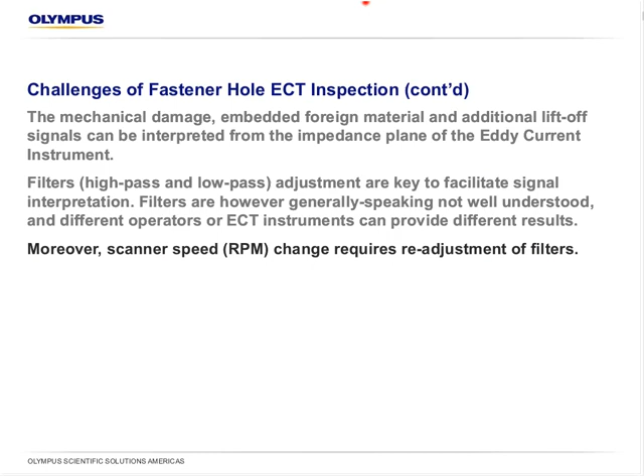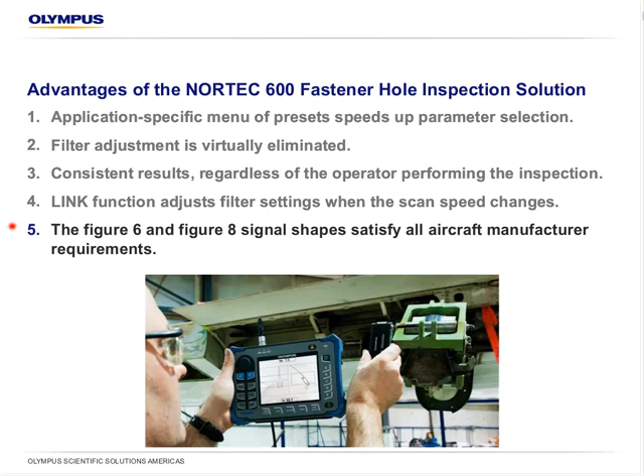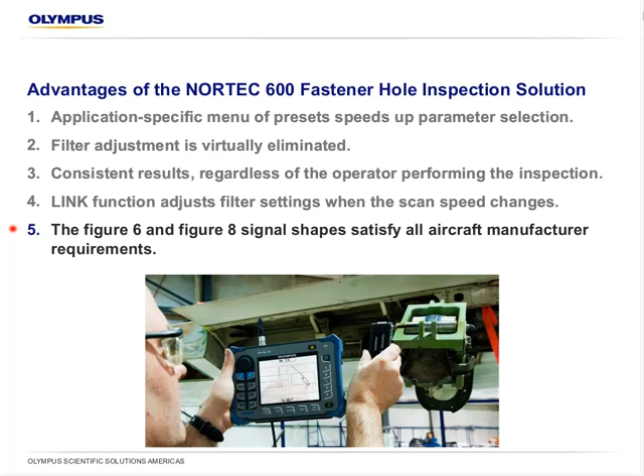So, the advantages of the NORTEC 600 fastener hole inspection solution. First of all, and I will talk quite a bit about it, it has an application-specific menu. Basically, it's presets that speed up the parameter selection. There is some filter adjustment possible. However, for the most common everyday use, the filter adjustments are not needed. They can be adjusted, but it's just not needed for most cases. The results are consistent regardless of the operator performing the inspection. There's a new link function that adjusts the filters according to the scan RPM, or rotation speed, of the scanner. Finally, we will learn about figure 6 and figure 8. Basically, the NORTEC 600 features those two signal shapes, and that contributes to satisfying all aircraft manufacturer requirements.